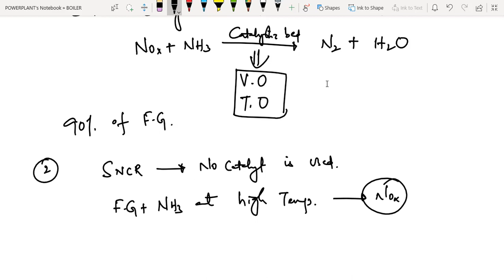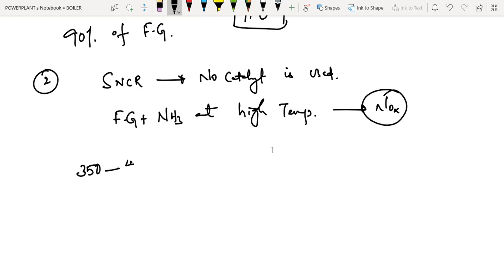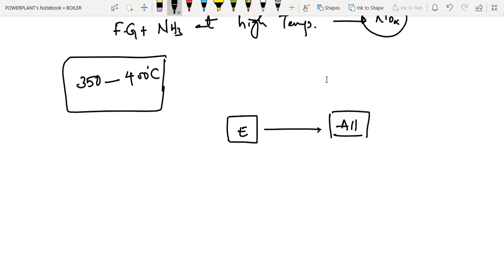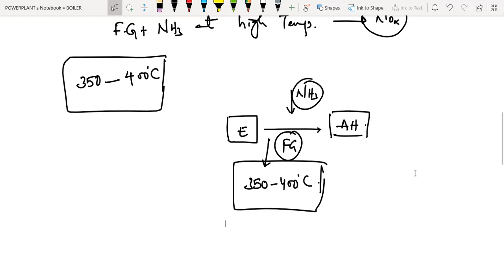One more thing is, for effective removal of NOx compounds, it is necessary to add ammonia to the flue gas at a temperature of 350 to 400 degrees centigrade. It is required to add ammonia at the outlet of the economizer and inlet of the air preheater. Here ammonia is added to the flue gas, because at the outlet of the economizer, flue gas temperatures will be around 350 to 400 degrees centigrade. As a result, we can reduce the NOx emissions from the flue gas.